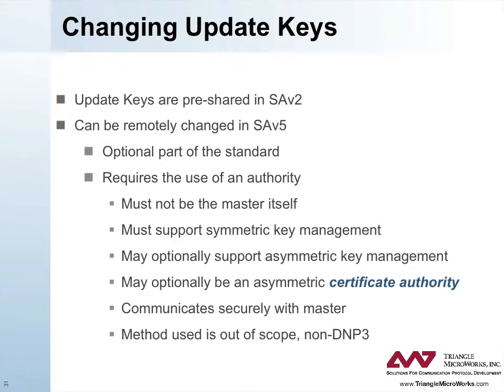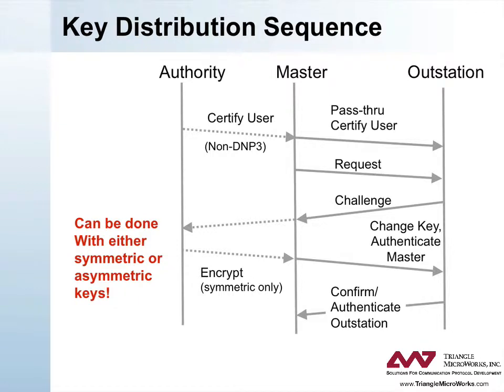In DNP3 Secure Authentication Version 2, or DNP3 SA-V2, update keys were pre-shared. DNP3 SA-V5 adds the ability to change the update keys remotely. This capability is optional and requires the use of an authority. The authority cannot be the master itself and must support symmetric key management. It may optionally support asymmetric key management and optionally be an asymmetric certificate authority. The authority must communicate securely with the master. The methods of implementing the authority are outside the scope of DNP3. The most likely solution is that the DNP3 specification will identify symmetric cryptography as mandatory and public or asymmetric cryptography as optional for changing update keys.